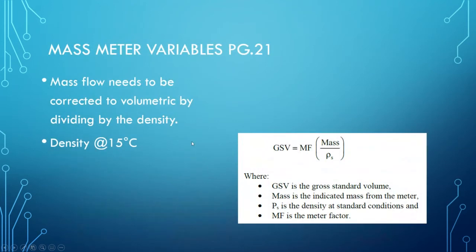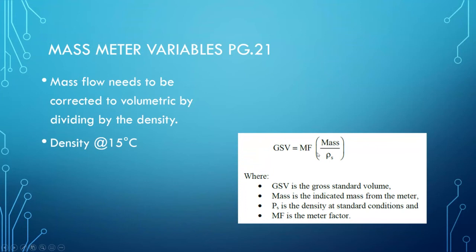For mass meter variables with liquids, mass flow needs to be corrected to volumetric by dividing by the density. Density is referenced at 15 degrees Celsius. The flow computer calculates gross volume by multiplying the meter factor by the ratio of mass to density at standard conditions. This is what the flow computer does for us automatically.